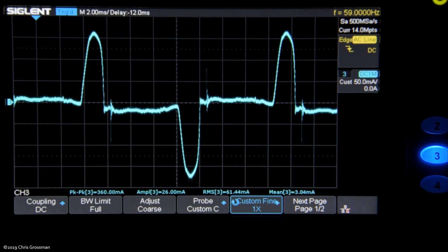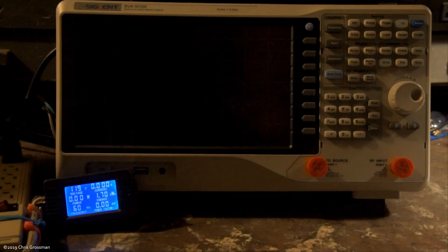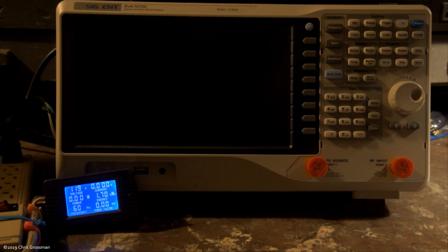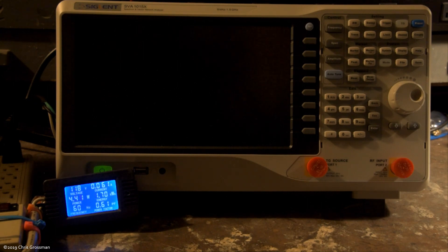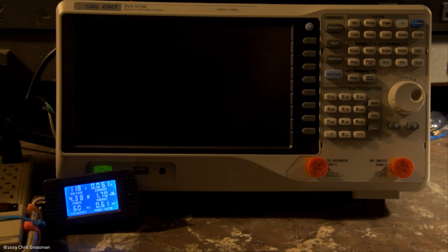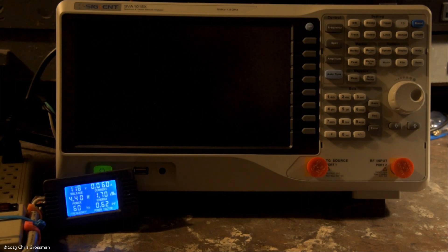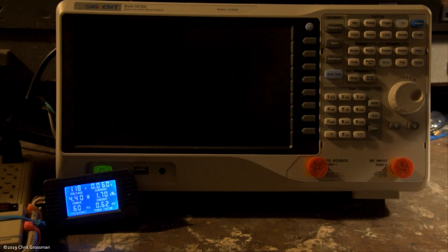But that's just the way it is. This is more power consumption video of the Siglent SVA-1015X spectrum and network analyzer. Right now it's in standby mode. Unless you unplug it, this is the power it draws all the time — it varies between 4.4 and 4.5 watts, 60 to 70 milliamps. Pretty high off-state power consumption. I confirmed with Siglent that it's not powering anything inside — it's not running a crystal oven to maintain stability. This is just off-state power consumption. So let's turn the unit on.